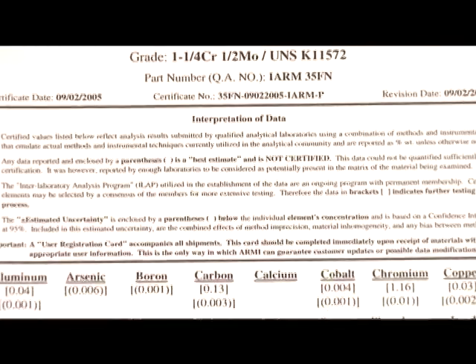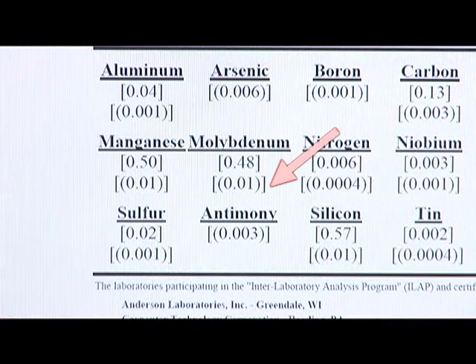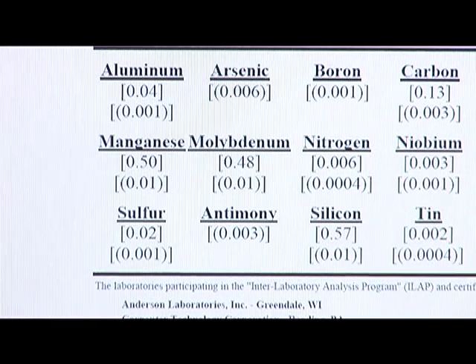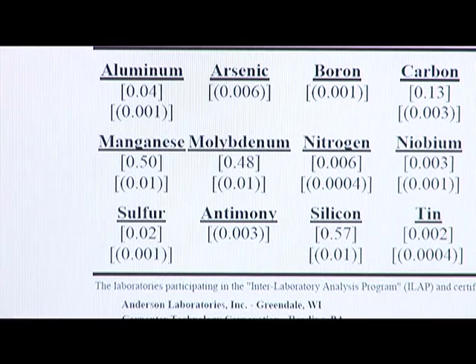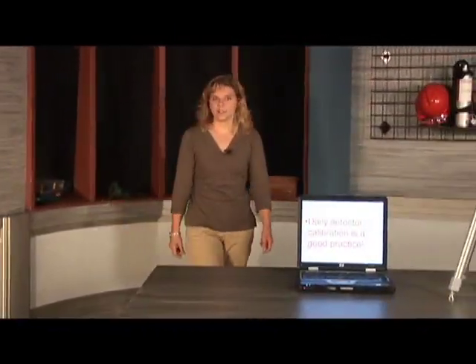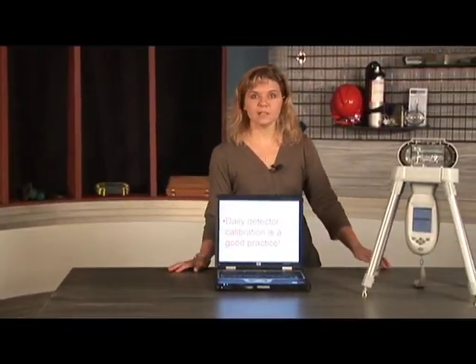As you will see from the certificate that comes with your check sample, the moly value includes an error of plus or minus 0.01%. If we add this to our low and high value, we will now be within 0.02% of the expected upper boundary value for moly. In a case like this, where we're so close to the decision value, even a rigorous lab quality XRF analyzer would be judged as close enough. However, we will perform a detector calibration in any case, as it is simply good practice to do so on a daily basis. This daily calibration will help prevent minor amounts of electronic drift from affecting your measurement results.